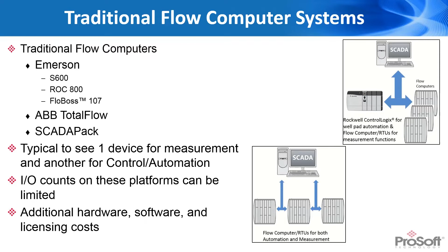The IO counts on those platforms were typically limited, so they didn't scale to the operation. As producers started bringing more and more wells into a single well pad site, the IO counts just didn't scale very well, so they had to add more and more RTUs. As you added more hardware, you also had additional software and licensing costs for each of these different measurement-related functions. So it wasn't necessarily scaling to the size of the operations, but also created a lot more additional hardware and software and revision control issues.